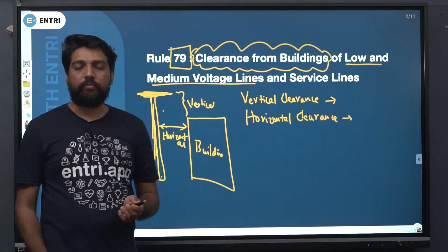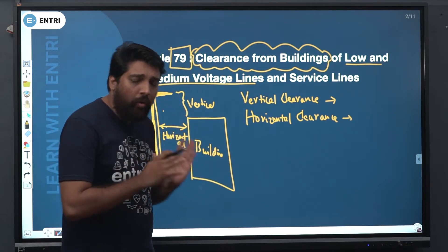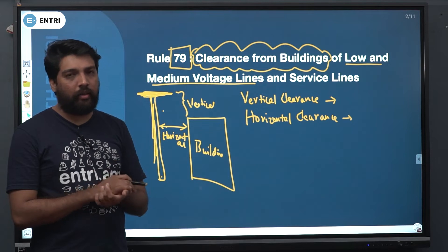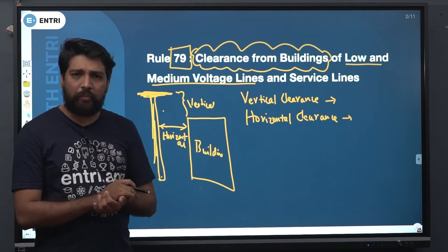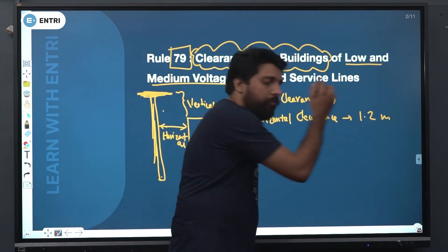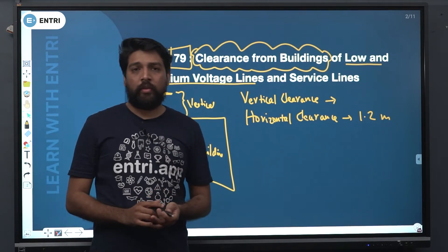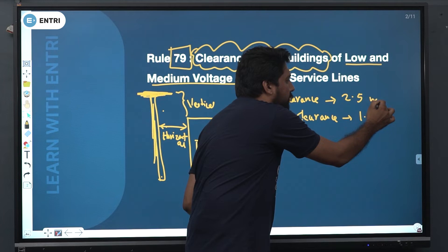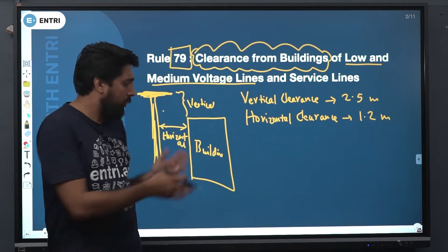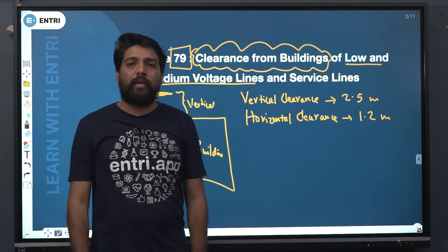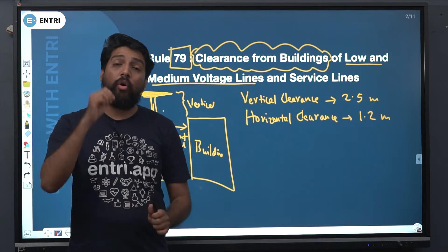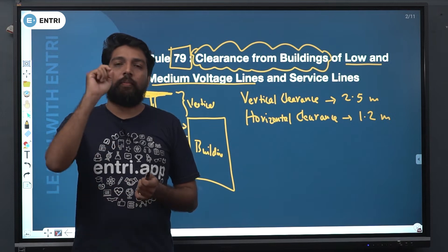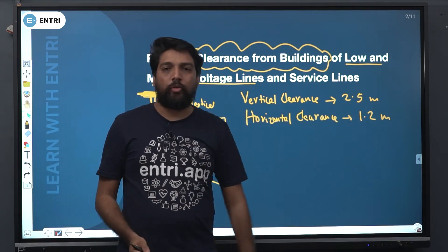Vertical clearance is vertical. In this low and medium voltage line it is exactly double — nearly double. Horizontal clearance is 1.2 meter and vertical clearance is 2.5 meter. So, clearance from buildings for your low and medium voltage line and service line: horizontal clearance is 1.2 meter and vertical clearance is 2.5 meter. Simple.